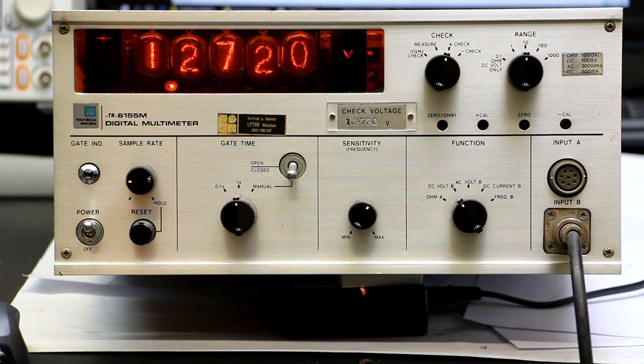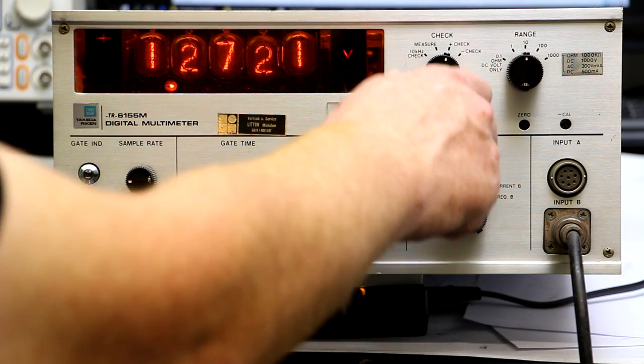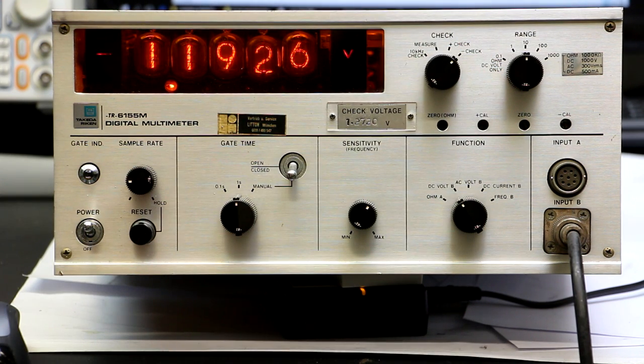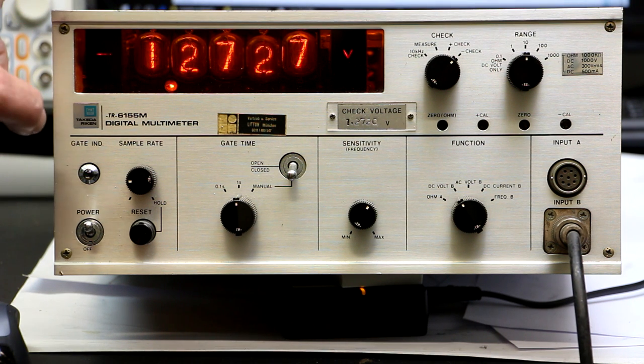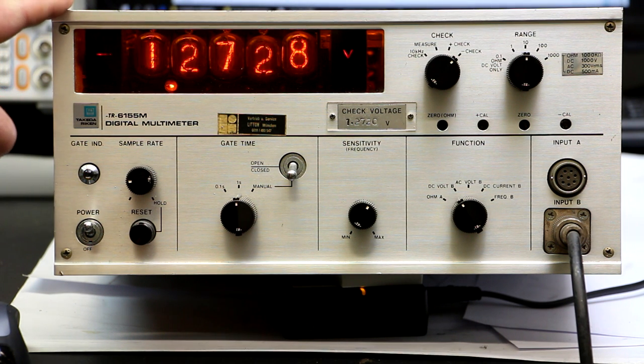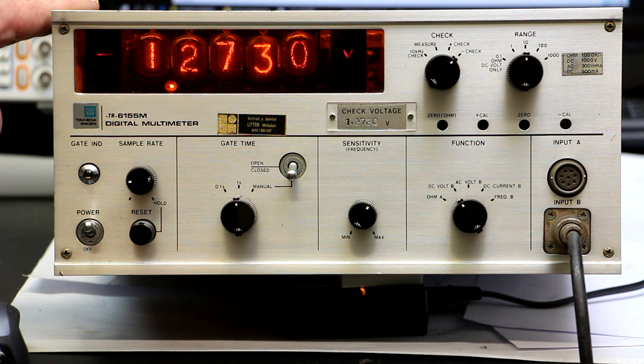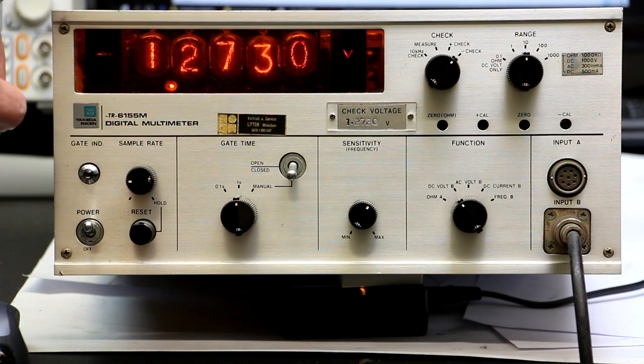.7220, just drifting around now. It has stabilized. The minus check, yeah, 5-7 digits out. So this might have probably drifted a little bit, but it might also be drift because it's not warmed up at the moment, and we don't have the outer case installed, so the temperature inside is quite different from where I made the calibration.